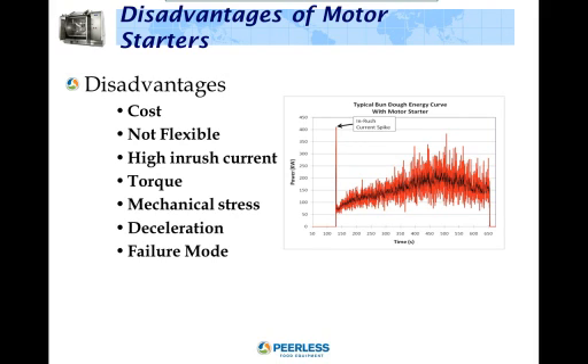Mechanical stress. The short acceleration time of the motor generates undue stress and shortens the life of the mechanical system being driven by the motor. Deceleration. No ability to decelerate the system with a starter. This could lead to issues related to safety guidelines. The failure mode. In the event the contacts weld shut, you lose the ability to shut off the motor. The motor may continue to run even after an emergency stop has been activated.